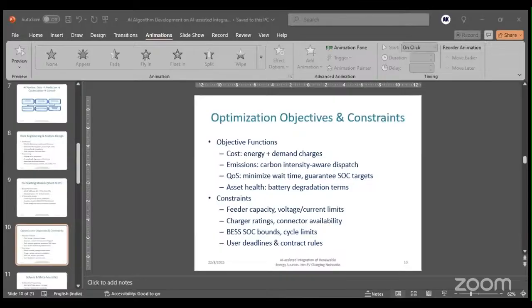The third is about battery energy storage system constraints. Especially we must know the boundary of the SOC, what type of battery is used, and the possible limits for charging and discharging. We must avoid charging and discharging above these limits, so the SOC must remain within safe minimum and maximum levels. Typically for lithium ion, we prefer 20 to 90% SOC. Below 20%, the battery management system (BMS) will stop discharging and give an alert to charge. Similarly, above 90%, it will not allow further charging.